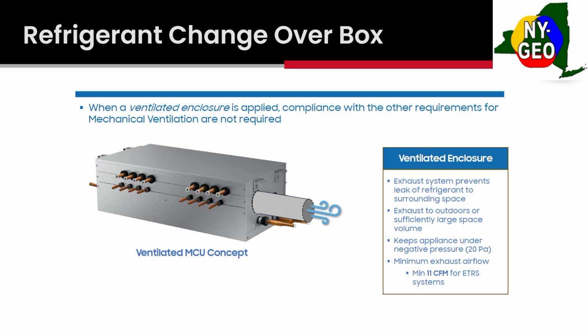And ASHRAE 15 sets a minimum exhaust flow rate of 11 CFM. So you've got to be conscious of where you are installing these in your building. You need to make sure there's an outlet. You don't have to exhaust it outside. You can exhaust into a larger space where there's enough volume to compensate for whatever refrigerant is in this box. And as the new equipment comes out with the new refrigerants, the VRF manufacturers are going to provide your selections that show how much refrigerant is in this box so you know what to count for in your calculations.